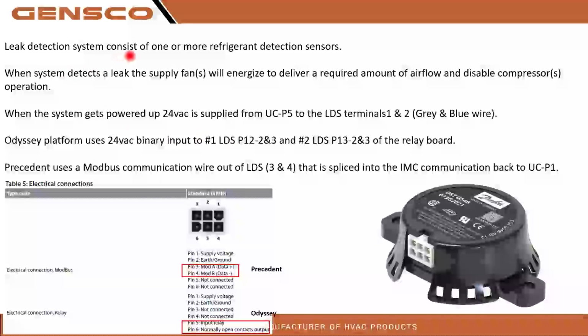The leak detection system consists of one or more refrigerant detection sensors. So when the system detects a leak, the supply fan will energize. You're going to disable the compressor and enable the supply fan. You're going to be able to change the amount of airflow as desired, but right now it's at 50% of whatever the tonnage is. And realistically, I think it was 500 CFM per 20 pounds of refrigerant. So it is pretty minimal airflow to dissipate the refrigerant.